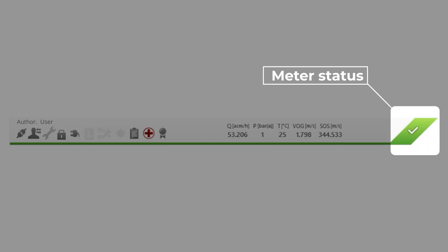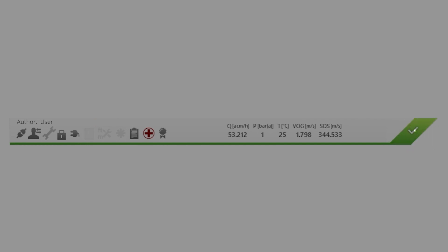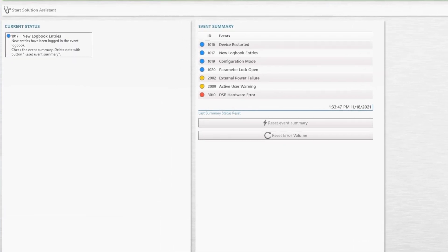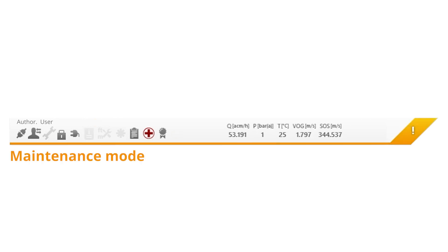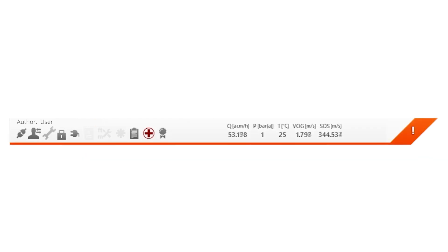The meter status icon, located on the right, uses different colors to indicate the meter status. You can click on the symbol for more information about the meter status. If the icon is green, your device is in operation mode with no errors, meaning the meter is working properly. If the icon is yellow, the device is in maintenance mode — the system has issued alerts, but the measurement results are still valid. If the meter status icon is red, a failure has occurred, meaning there were errors and the measuring results are no longer valid.